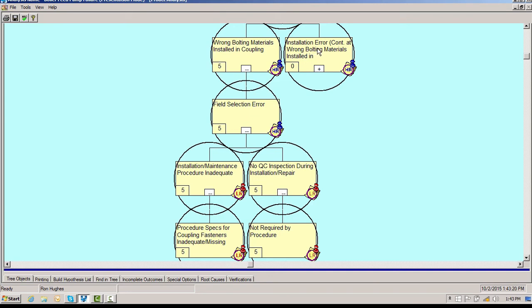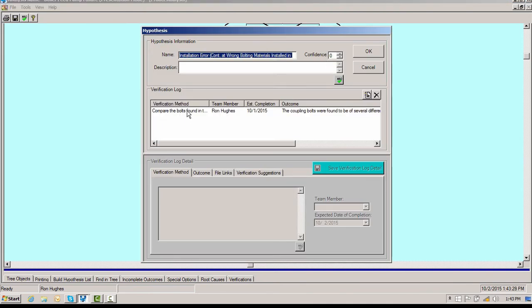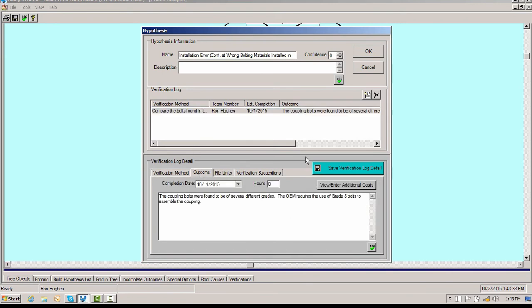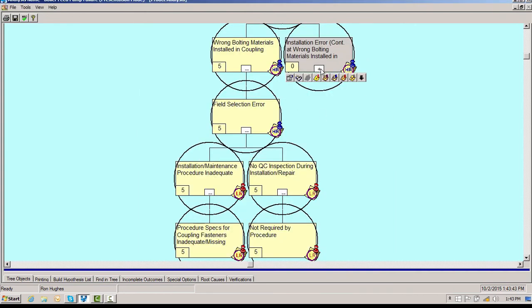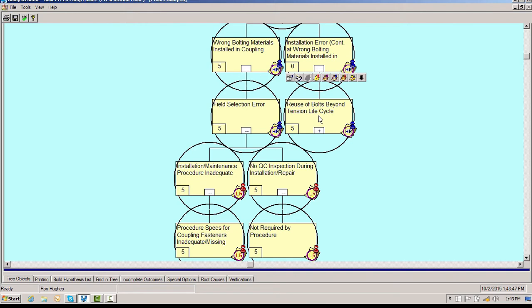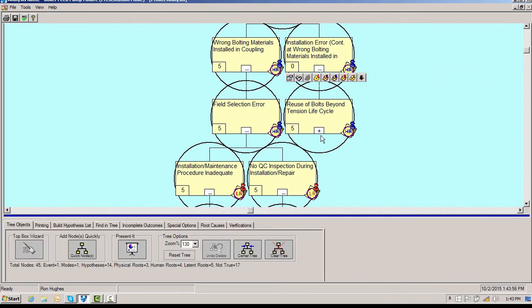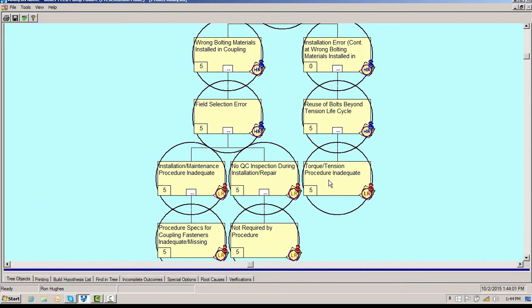We also have an installation error — not only were the wrong bolts installed, but the OEM recommends that you not reuse these bolts more than once. When I got to seven times reuse on these bolts, I quit counting. The bolts were reused beyond their tension life cycle. Bolts are not perfect springs — you just can't keep re-torquing and reusing them. The torque tension procedure is inadequate because in actuality there is no torque tension procedure. It's not the amount of torque you put on a bolt — it's the amount of tension in the bolt that determines clamping force, which is what you're actually measuring for slip resistance of the contact surfaces in the fastener assembly.